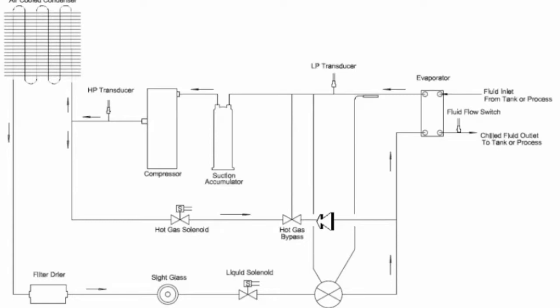Now, the main benefit of a hot gas bypass system, there's actually two. First, it prevents potential freeze-ups of your evaporator. And this can happen when somebody tries setting the set point of the chiller lower than it should be. And that can cause a catastrophic failure of the chiller's evaporator and excessive downtime.